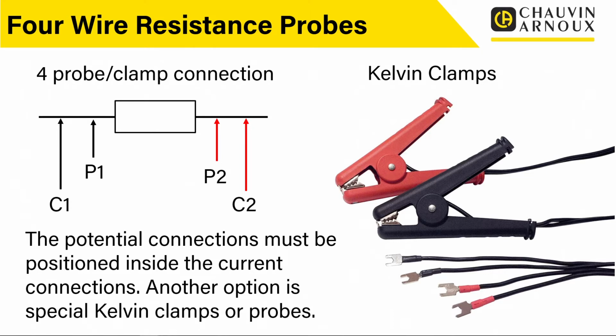So best practice is to use 4 separate connections, and then we can position those and get some really good contacts. But that isn't always possible. When you're measuring things, you might only have access to a particular terminal or screw head or some sort of test point that you're actually measuring at.